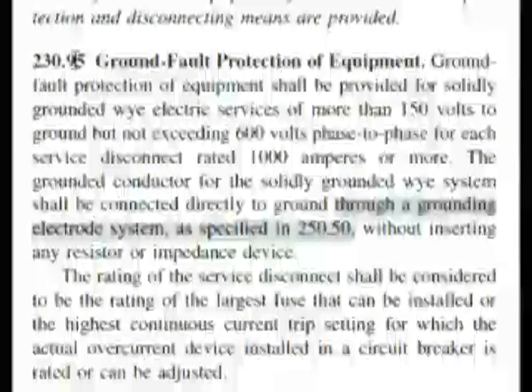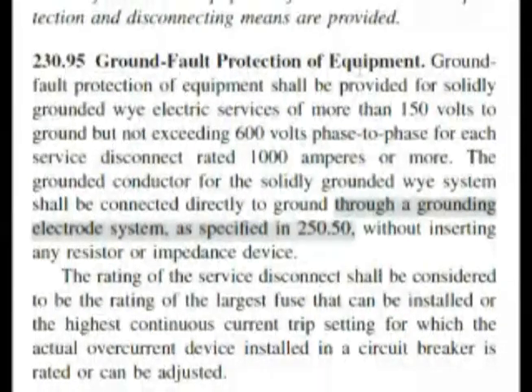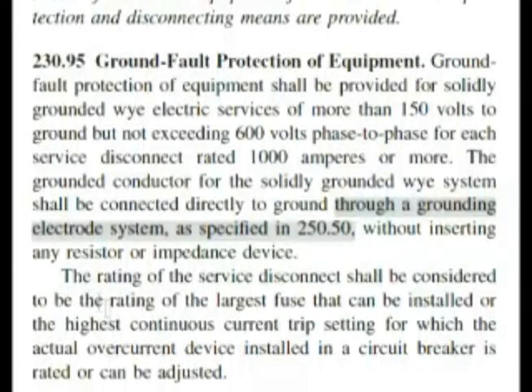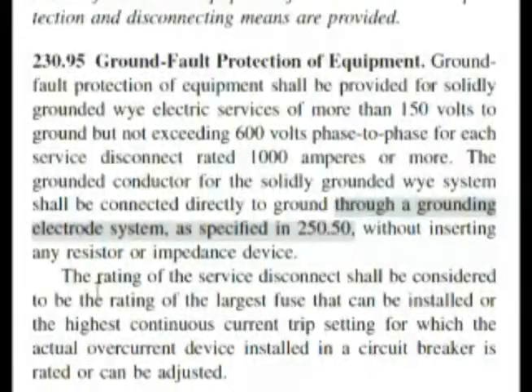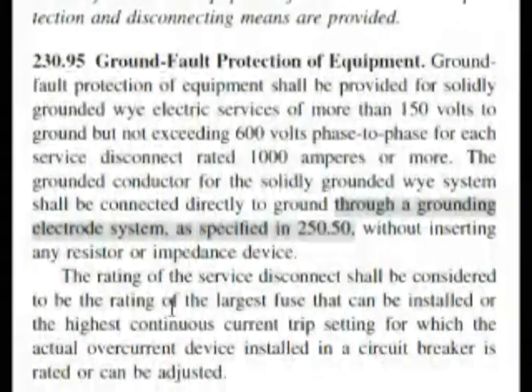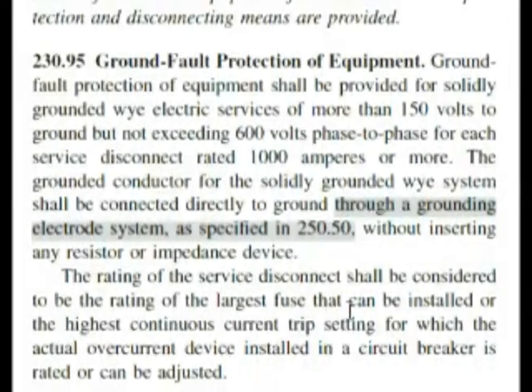Let's go right here to 230.95, because they're saying it's defined by this. Let's go right here in the codebook. So 230.95 is talking about ground fault protection of equipment. Now if you read down the second paragraph we have here, it's almost word for word. The rating of the service disconnect shall be the rating of the highest or the largest fuse that can be installed.